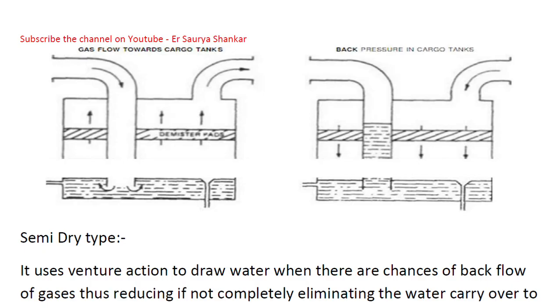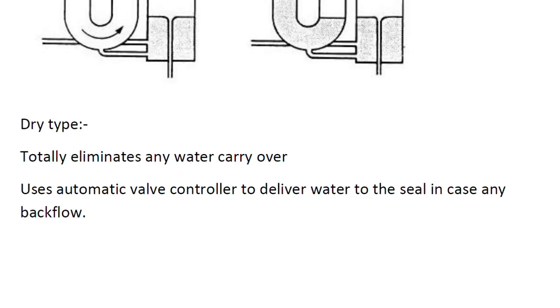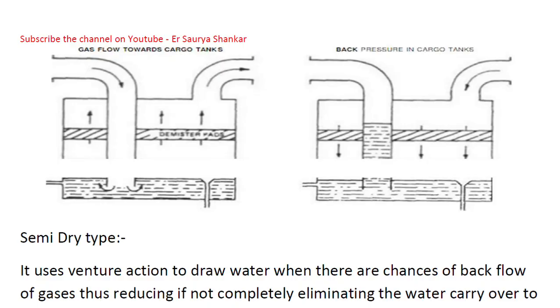Looking at the diagram, it consists of a chamber filled with water and two pipes for inlet and outlet of flue gases, while another two small pipes denote inlet and outlet for sealing water. There is a demister pad to remove water droplets from the gas. The two diagrams show conditions where the inert gas is flowing from the plant to the distribution area, and where back pressure tends to push cargo gases into the IG system and is prevented by the water seal.